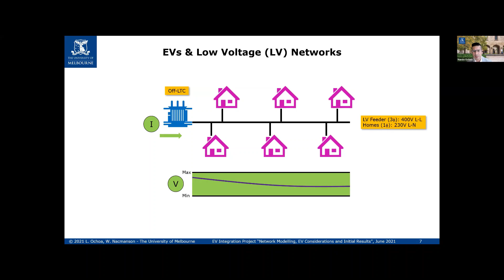We multiply by the number of houses, produce some factors, and that's how we design the transformer and the length of that particular circuit, all to ensure that during peak demand, all the currents stay within the capacity of the assets—conductors, transformers—and the voltages stay within the statutory limits of that part of the world.